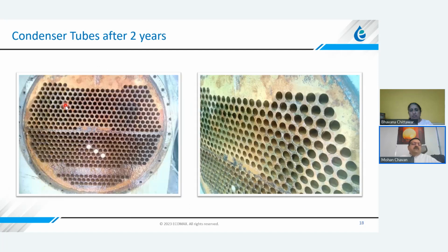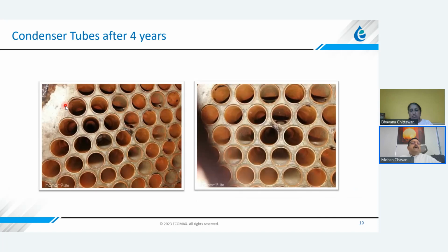This is another example wherein we found the tubes clean even after 2 years. This one is one of the IT companies. Even after 4 years, the condenser approach was maintained below 1 degree F. See, the key for this technology is we need to maintain the cleaning sponge balls in circulation in the system. Then we don't have to look back for manual cleaning of the system. Many times after these systems are installed, people neglect changing the balls, and that's where the scaling can happen again.